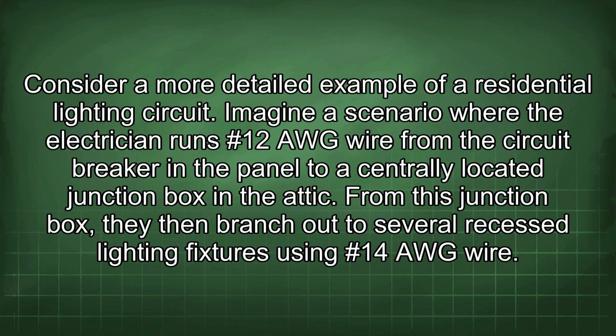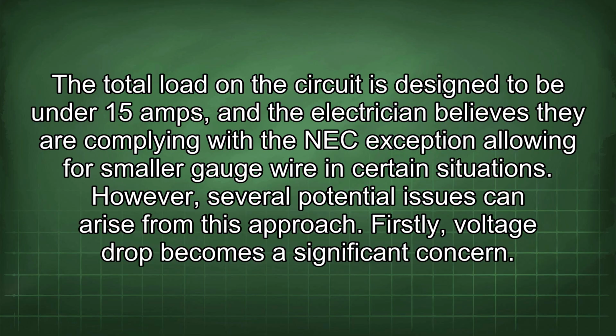Consider a more detailed example of a residential lighting circuit. Imagine a scenario where the electrician runs #12 AWG wire from the circuit breaker in the panel to a centrally located junction box in the attic. From this junction box, they then branch out to several recessed lighting fixtures using #14 AWG wire. The total load in the circuit is designed to be under 15 amps, and the electrician believes they are complying with the NEC exception allowing for smaller gauge wire in certain situations.